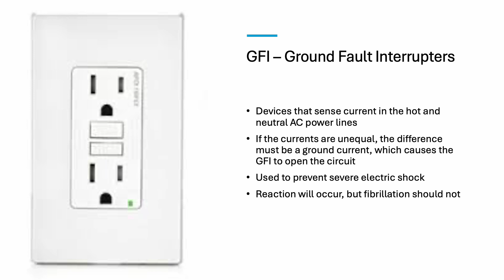Whenever the device is tripped, a red light comes on and all you have to do is hit the reset button for the outlet to work again. The other button is to test it. It simulates a ground fault, and it should click and show a light, and then you can reset it again.